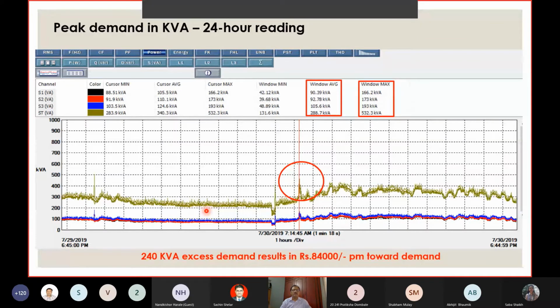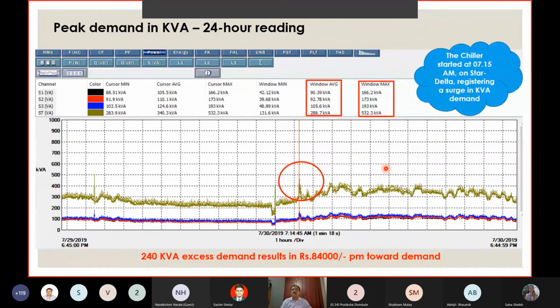It's a child hospital, so during the nights the temperature would be kept slightly warm. They will not run the chiller. But in the morning, as soon as they come and start other preparations and operations, they would have switched on the chiller. And this sudden switching on is a star-delta starting. So the sudden switching on of this chiller at 7:15 a.m. using a star-delta starter has registered this peak.